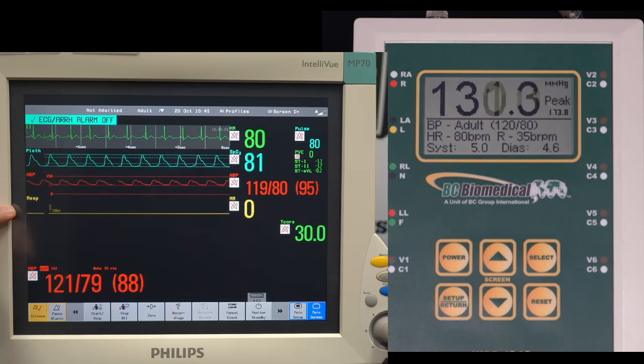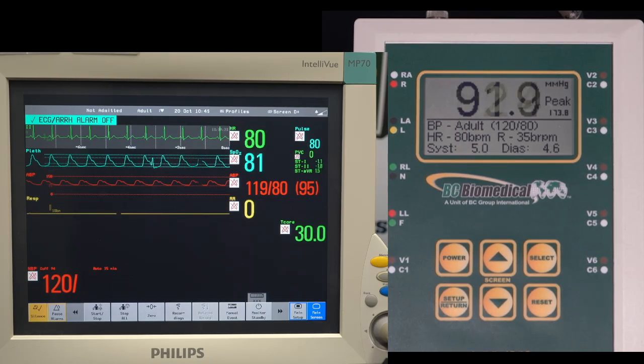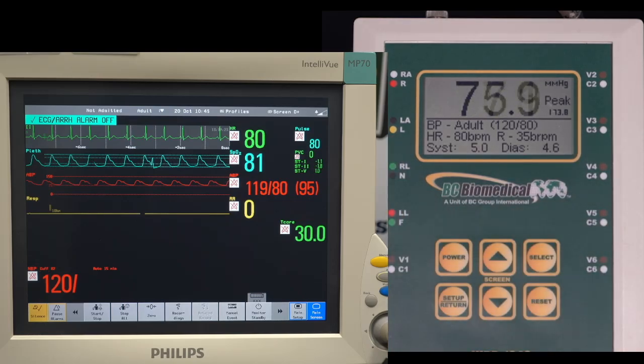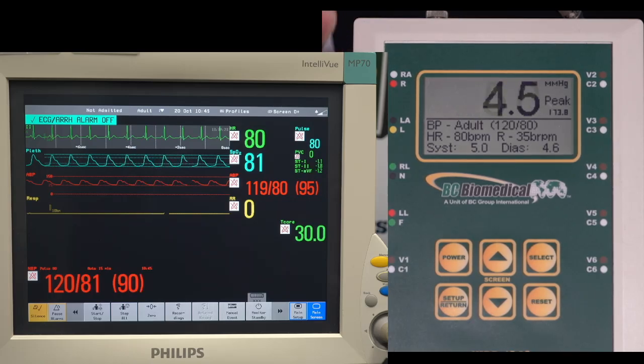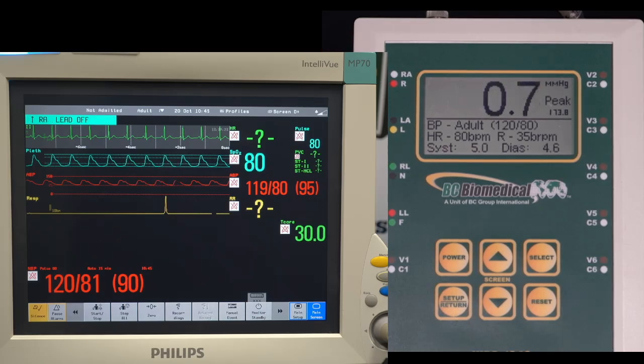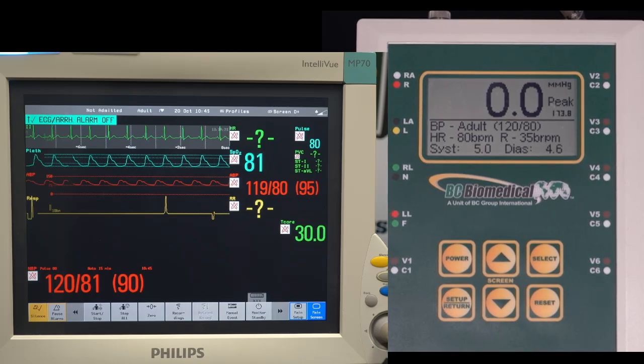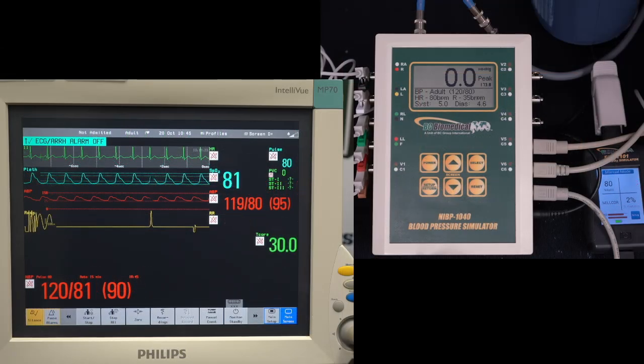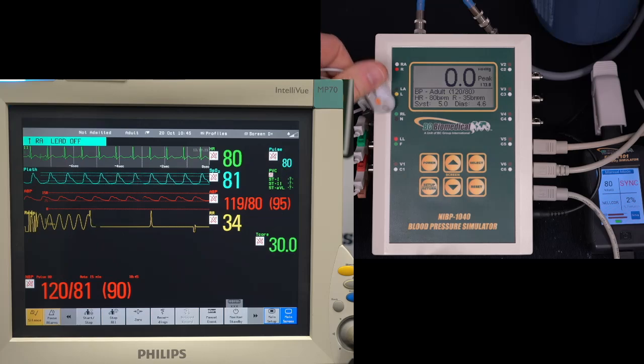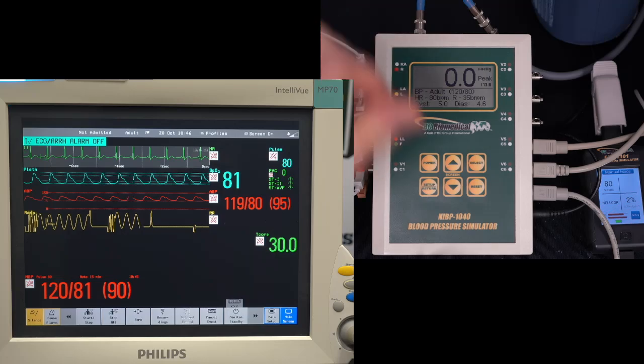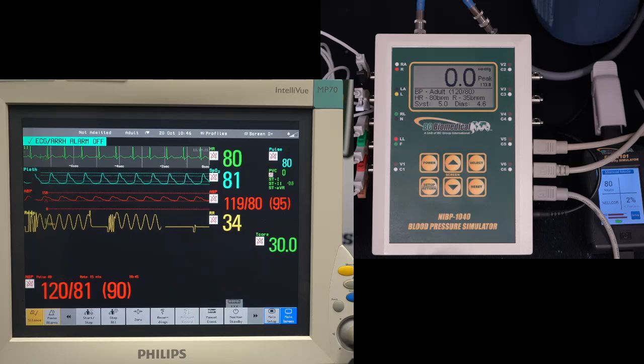I mentioned the respiration. We've got nothing shown for respiration here. Now, some monitors measure off of the left arm, some measure off of the left leg. For this NIBP, we only have the option to, we have that simulation in the left arm. So if we reverse, we can just reverse our leads here. By reversing these leads, I've also got this on a view that you can't see. So these are the ECG leads here. This was the black one for left arm, and this is the white one for the right arm. So all I did was reverse these over here, and that puts the respiration signal in the correct lead so that the monitor can see that. And now we've got respiration visible on the screen.